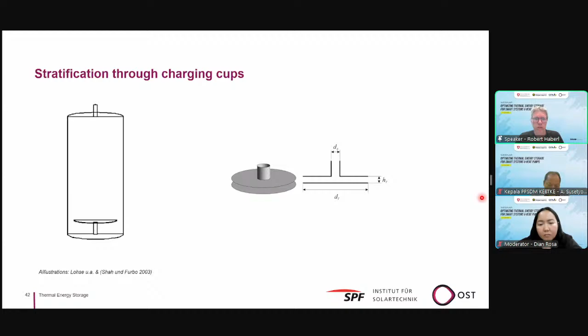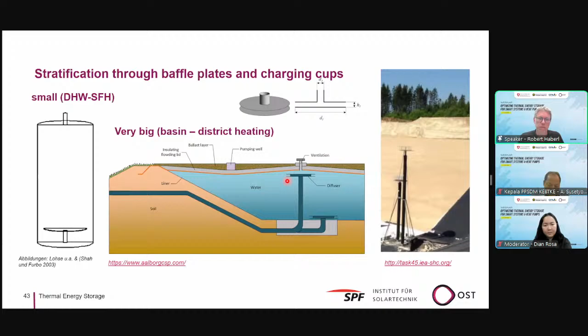And there is a different part for bringing in and out water, the so-called charging cups. They are used in very big storage tanks or in basins, and they allow the fluid, if you have a baffle plate, to get out on the diameter of that baffle plate, and that is a very good means to slow down the velocity and keep your stratification good. So the general recommendations for the construction are a speed below 0.1 meter per second. That is crucial, and a length of at least 6 times the hydraulic cross section of the pipe to allow the fluid to calm down.